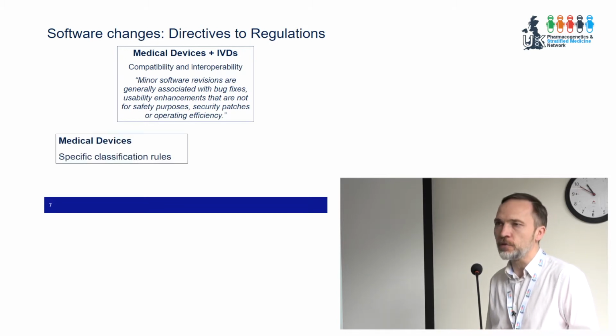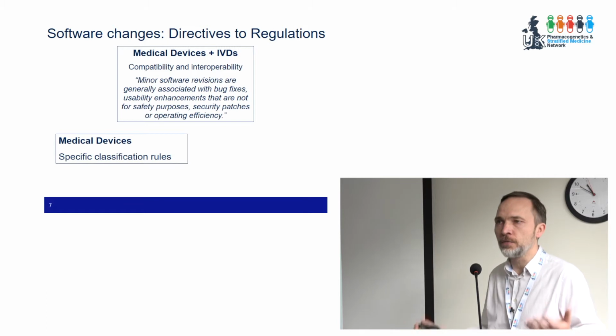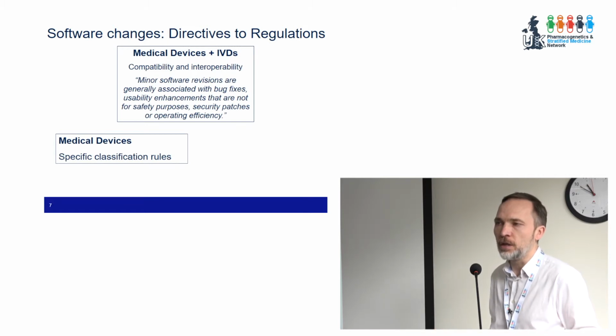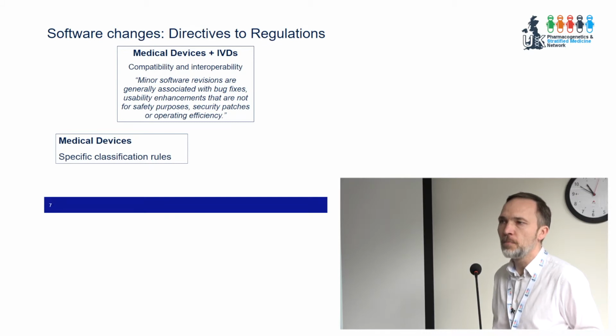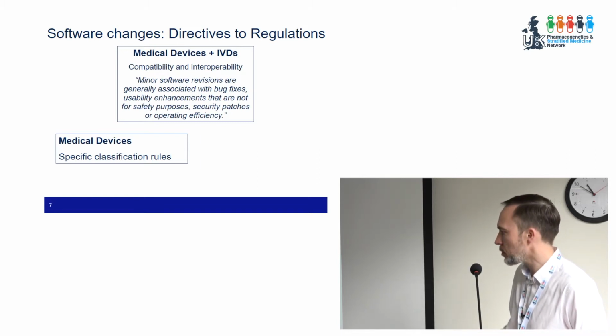Medical device regulations introduce specific classification rule for software. So again, whether it's an IVD or a medical device, everything's going to be up-classified. There's going to be a lot less software around which is self-certified by the manufacturer. Most of it will now have to have some kind of notified body scrutiny before it can get a CE mark and be placed on the market.